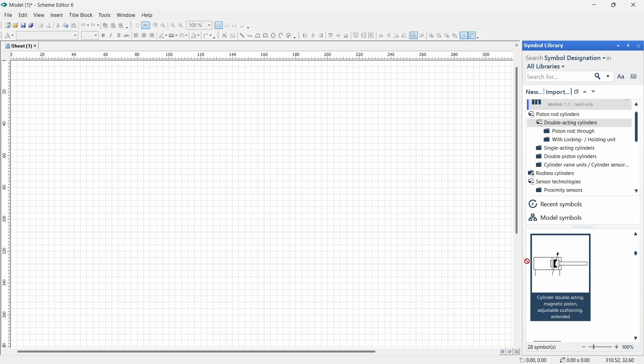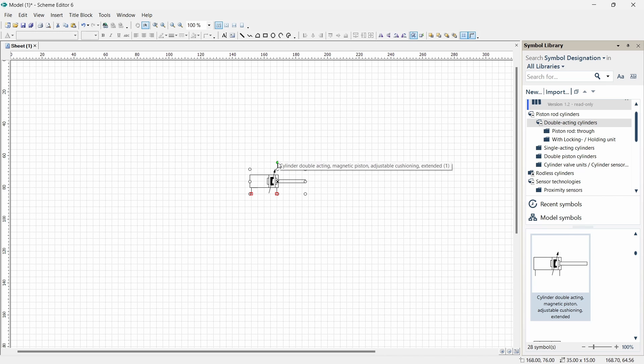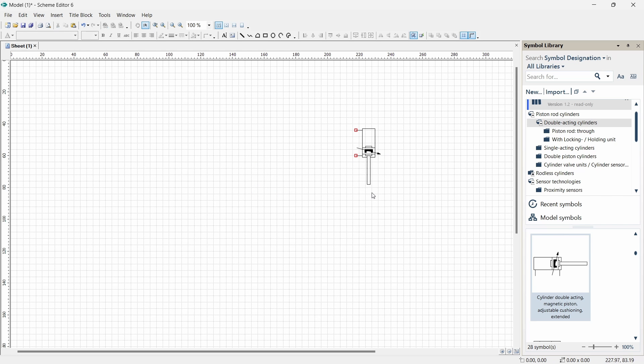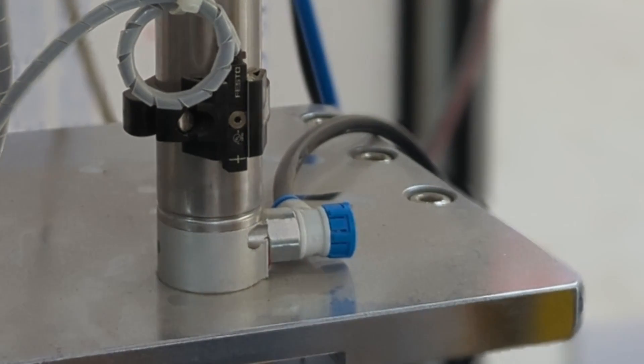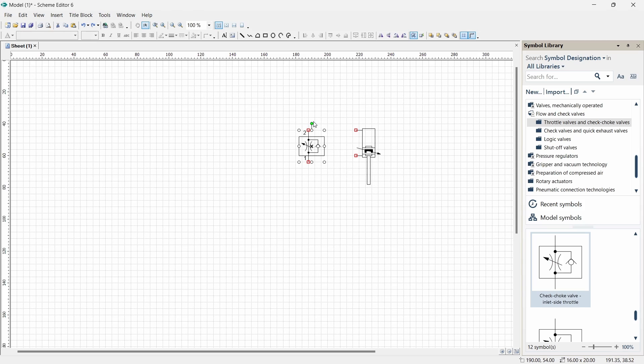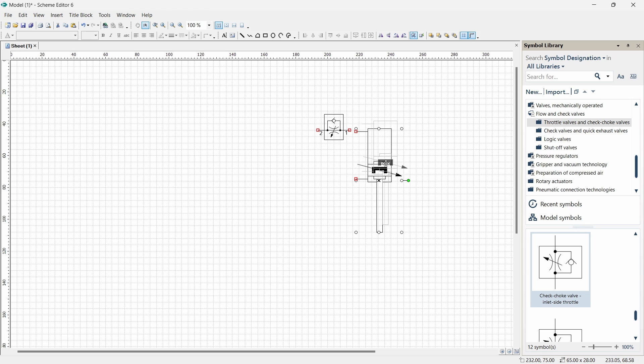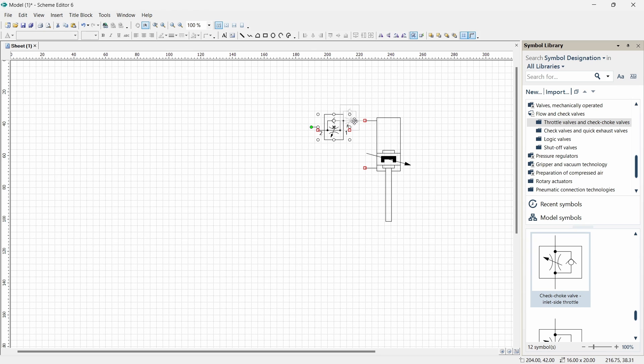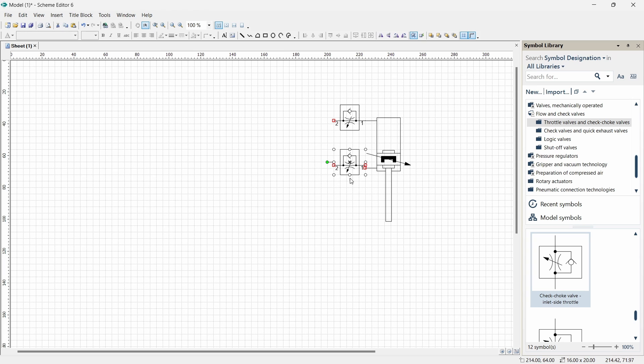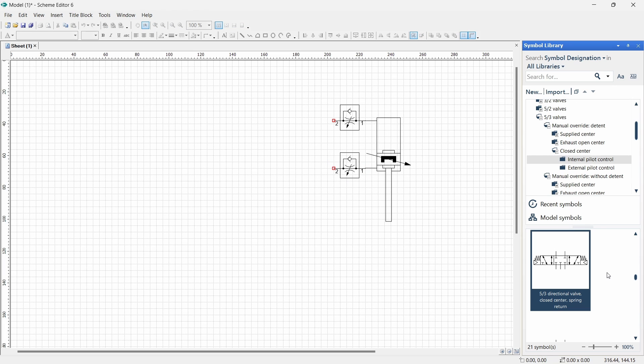Let's start drawing the circuit for the press system. I am dropping a dual-acting pneumatic cylinder with a magnet piston and air cushion, rotating it and placing it on the right side. Then I am adding speed controllers, setting them to meter-out position. I place one speed controller near the cylinder port and enlarge the cylinder symbol as needed. Then I copy the speed controller — hold Control and drag — and connect the second one to the other cylinder port.